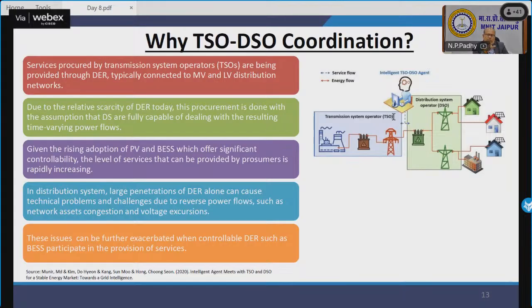Imagine in the distribution network, renewable generation is more than the consumption now, you have enough DGs. So what will happen? The energy will flow in reverse, from 33 kV to 132 kV to 230 kV. At that time, the TSO will reduce buying power from the transmission systems. Are you getting my point? That is how the TSO-DSO interaction mechanism works.